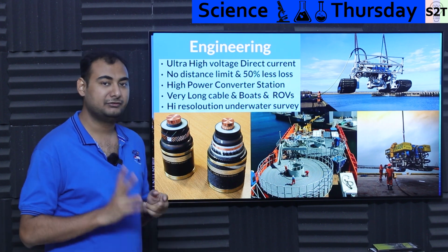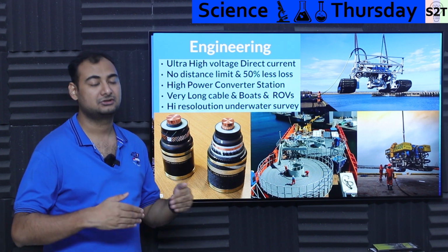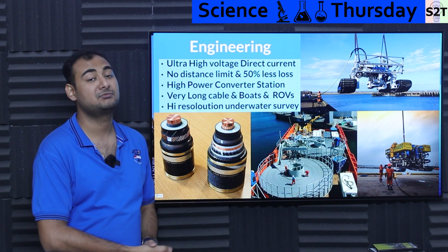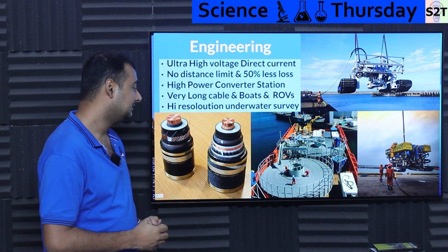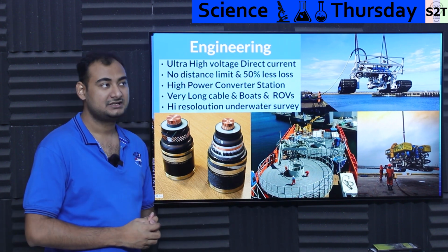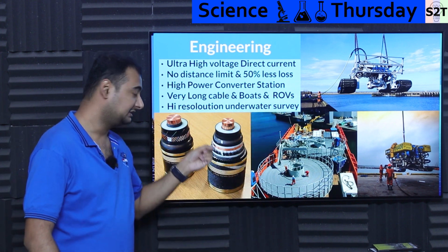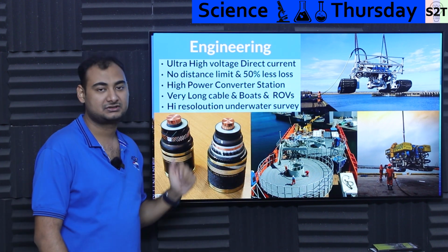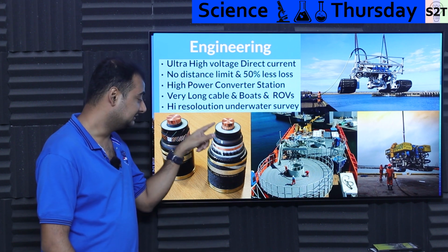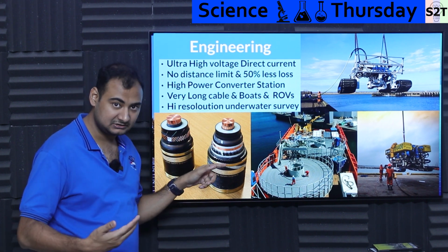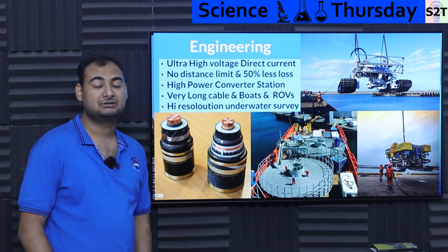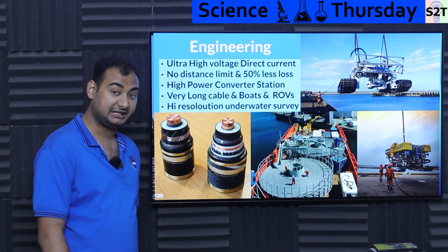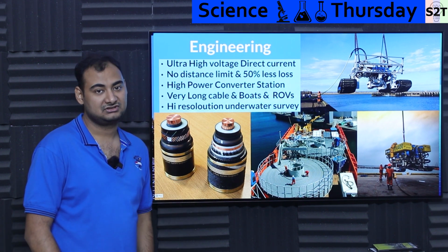Well, there are two vectors you control - voltage and amps - in order to control how much oomph, or watts, you can transfer from point A to point B. Now, why don't you just increase the voltage? Well, you can increase the voltage as much as you want in the air, but here, if the core is designed for 300 kV and the insulator is designed for that stress load, if the core starts carrying 500 kV, the insulator will simply go boom.